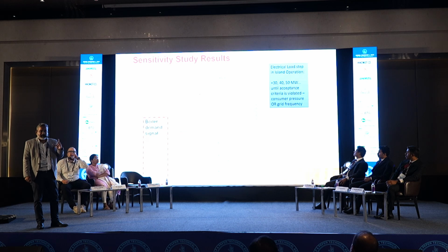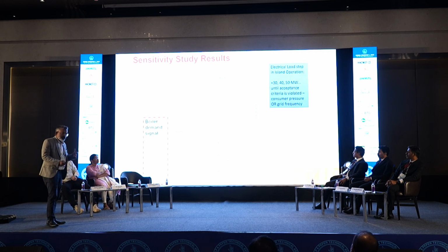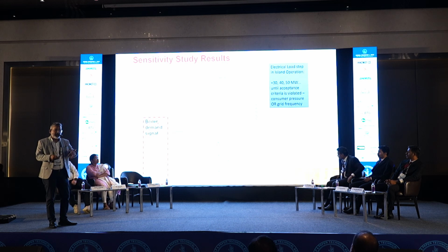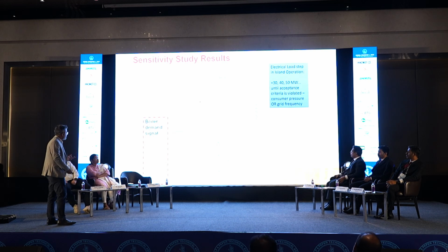So the maximum load swing the plant can handle is up to 70 megawatt. So this is what it answers, that is how you find your operational limits. And within those operational limits, how you prepare your operational strategies, that is what we have suggested.